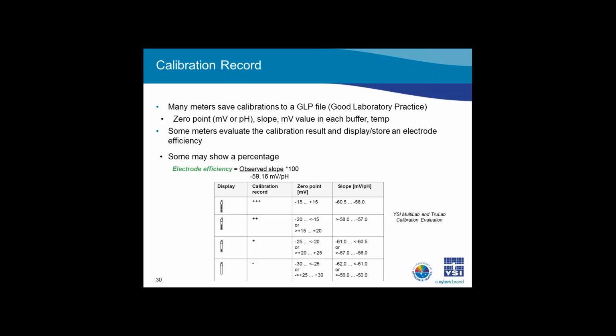As the efficiency nears 90% or lower, you should consider servicing the sensor. That is, of course, after making sure you're following all the necessary steps to ensure a proper calibration. We don't want to service the electrode if it isn't necessary, so start by troubleshooting and verifying your calibration by verifying the buffers and the routine that you're using.